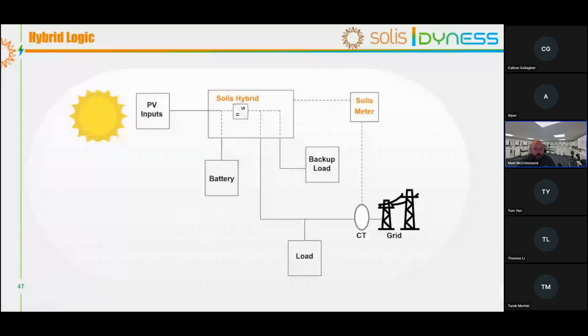Hybrid logic. So we've now put the inverter into self-use. So the inverter's job now is to reduce your energy costs. So basically that's determined by the Solis meter. So the Solis meter reads the CT and decides is the energy importing or exporting. So if we're exporting energy, then the hybrid inverter knows to put that much energy into the battery on the DC side.